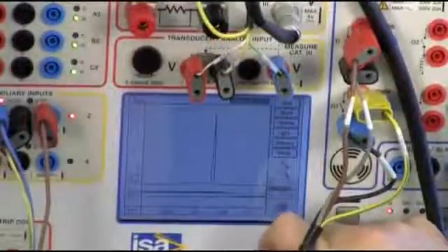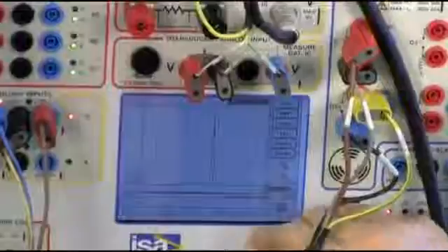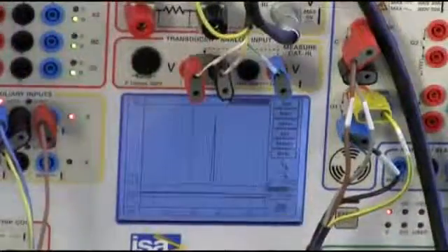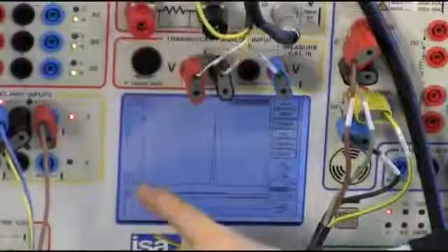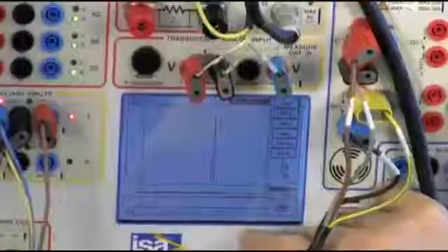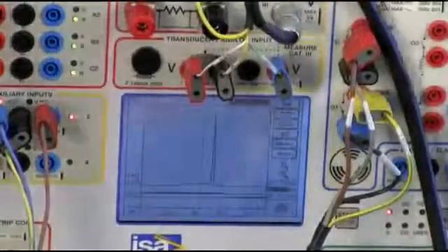Now, have a look. I select again this cursor. As I move the cursor, it is telling here, in terms of milliohm, the resistance that it is measuring. And look, 0.615, it is just the contact resistance that we had measured during the contact resistance test. You see? 0.61, 0.62, okay.